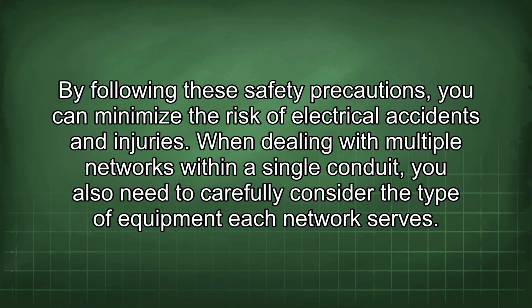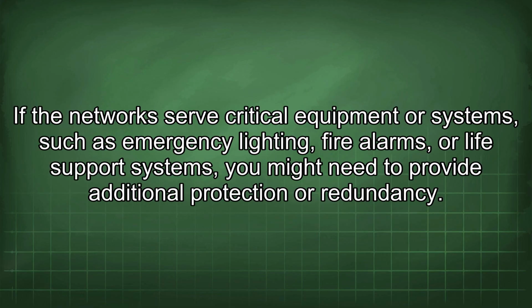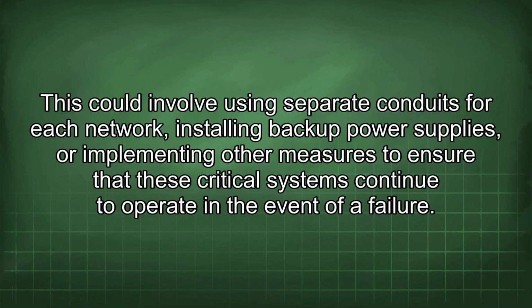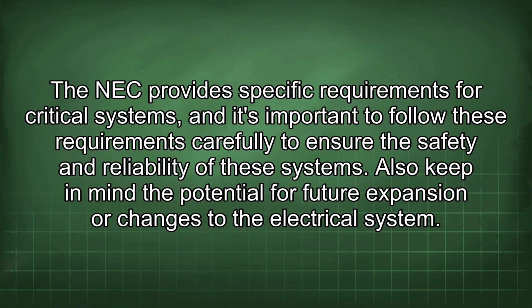When dealing with multiple networks within a single conduit, you also need to carefully consider the type of equipment each network serves. If the networks serve critical equipment or systems such as emergency lighting, fire alarms, or life support systems, you might need to provide additional protection or redundancy. This could involve using separate conduits for each network, installing backup power supplies, or implementing other measures to ensure that these critical systems continue to operate in the event of a failure. The NEC provides specific requirements for critical systems, and it's important to follow these requirements carefully to ensure the safety and reliability of these systems.